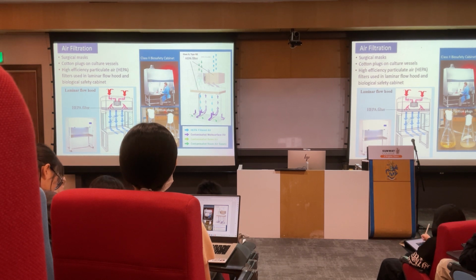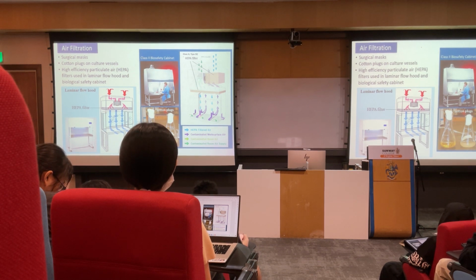How does the biosafety cabinet work? There are two HEPA filters. One is placed here, similar to this. So the dirty air comes in and goes through the filter. The air that comes down here is clean. However, it will not come out through the front because you are sitting in front of it. So it wouldn't come out.